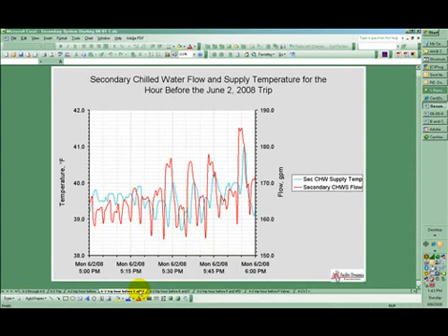And basically what you can see is that there's a very strong correlation between the flow and temperature. So what that means is that flow instability triggers temperature instability, and that temperature, as you can see right here, flirts with the freeze-stat trip setting. Right there, it does it right there. And this goes to the issue Walt's been mentioning, that the chillers really are just protecting themselves from an issue that's caused by some other thing going on out in the system.